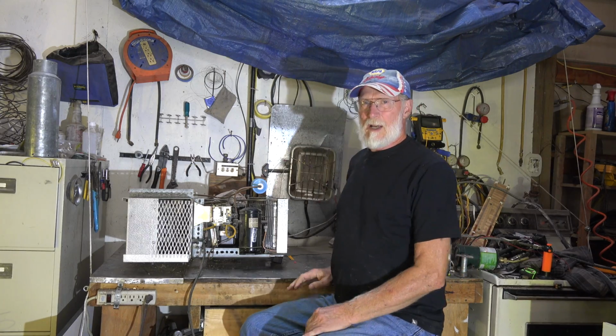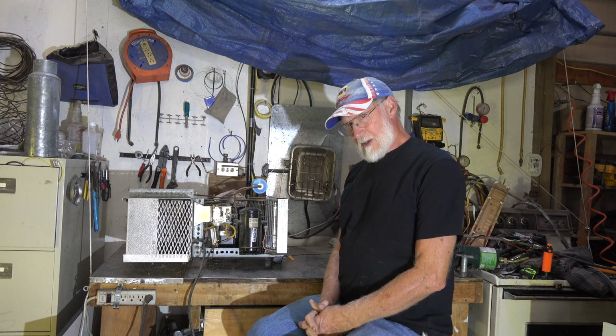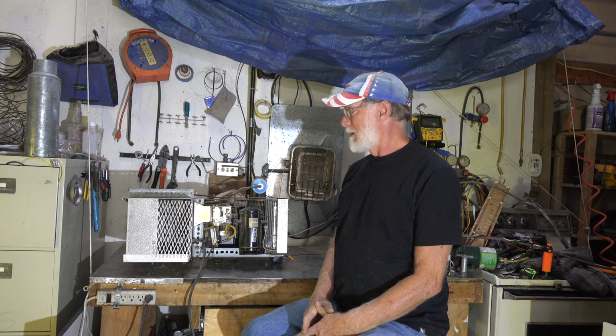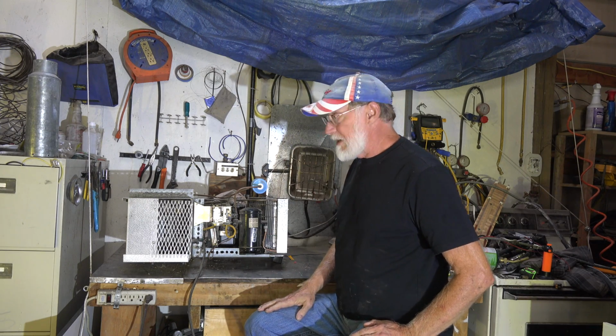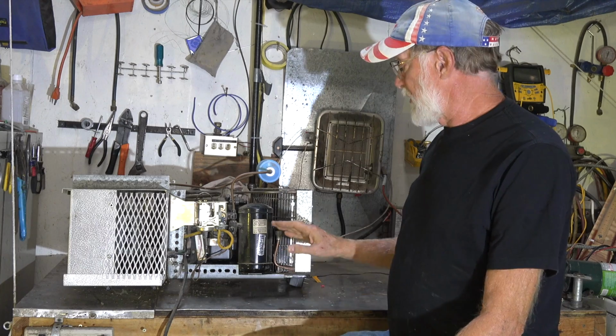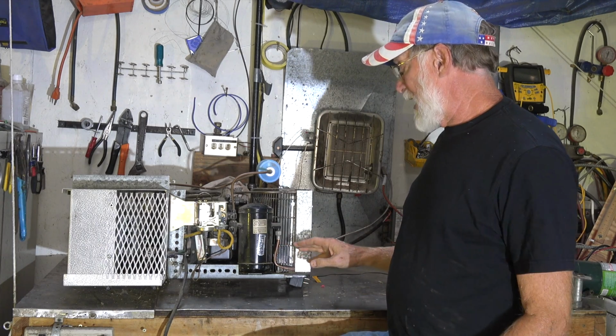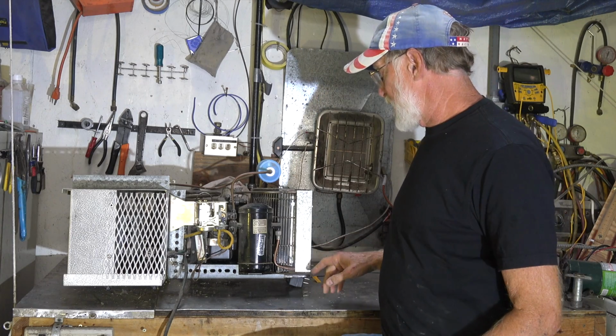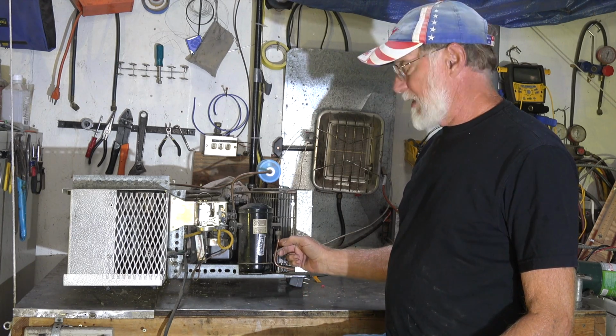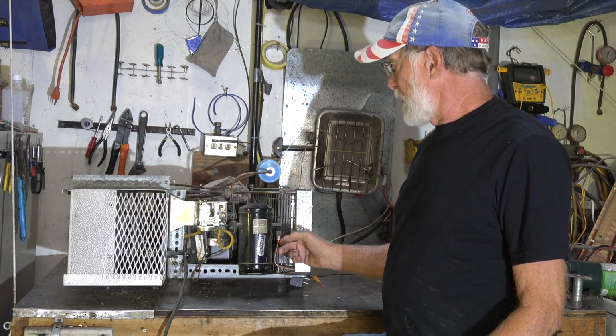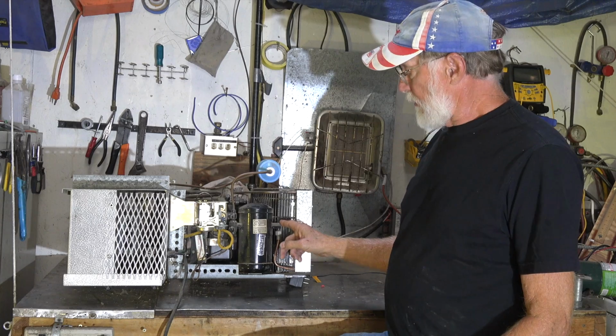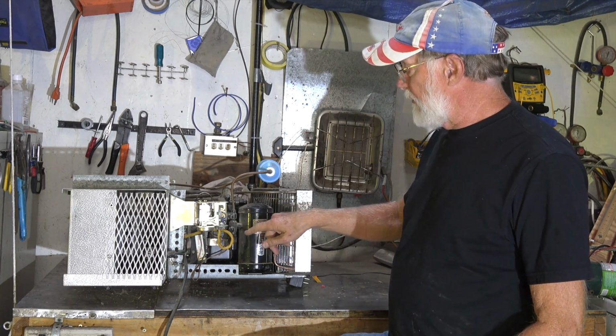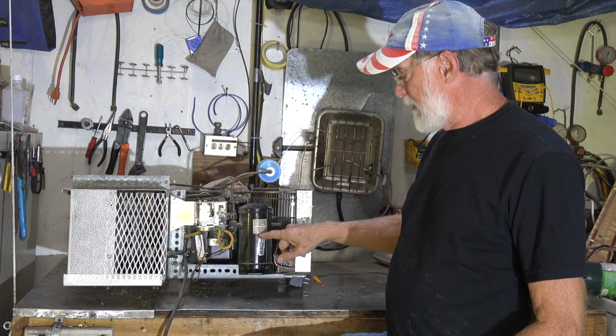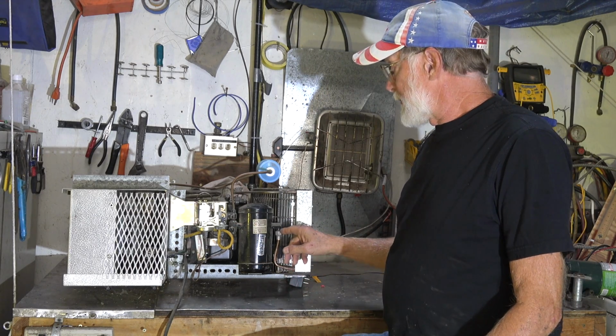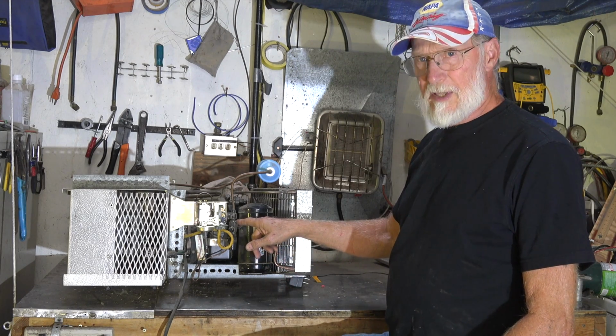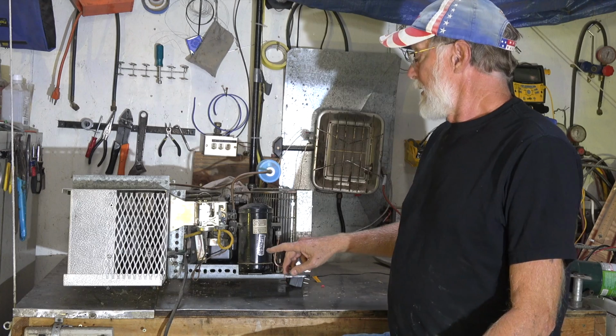In this one, I wanted to talk about the difference between the charge compensator and the receiver. Well, here's a little refrigeration system with a receiver on it. The receiver is usually mounted pretty close to the condenser. We have condensed liquid refrigerant coming into the receiver here, dropping down to the bottom. There's a dip tube on the outlet that goes down to the bottom, so liquid refrigerant can come out of this as long as there's any refrigerant in it.